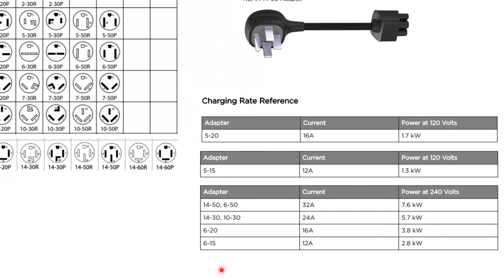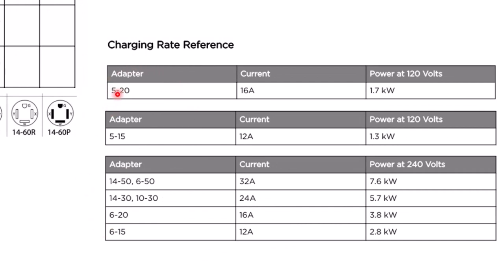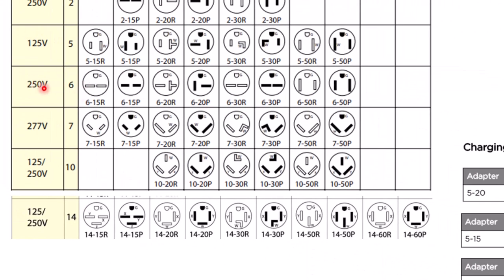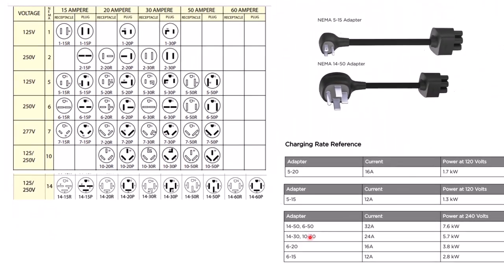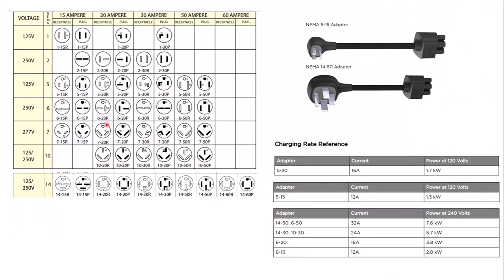And you can see the adapters available. They have the adapters for the 5-20, the 5-15. They even have it for the 6s. And the 6s are just a 250 volt rating, without the 125 volt here, as shown in the NEMA 14. It's just a 250 volt rated receptacle. And these are the plugs, right? So if you have this type of receptacle, you would have to purchase this type of adapter to fit that NEMA 6 rating. And for these, you could see that there's one that's rated a 10.